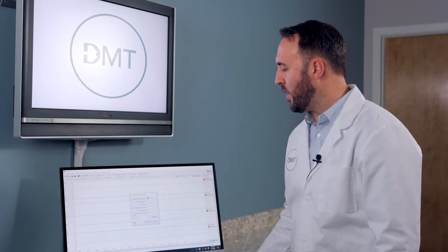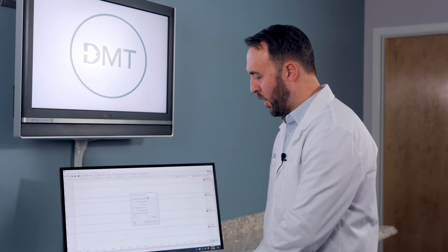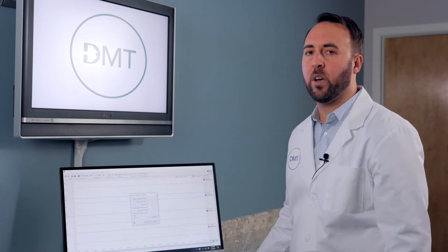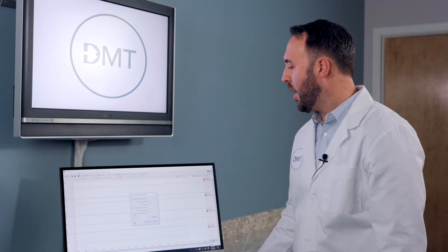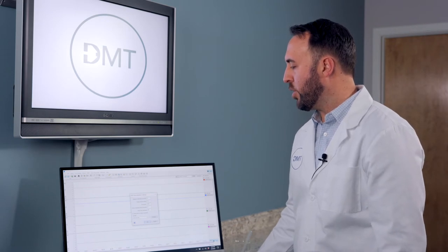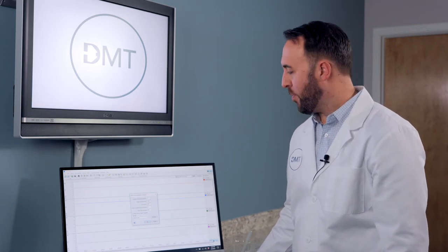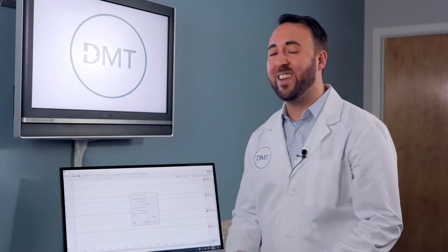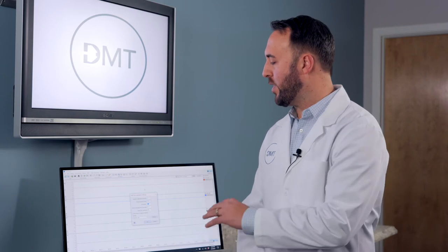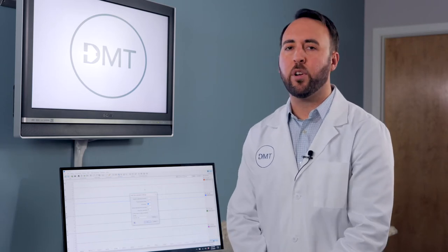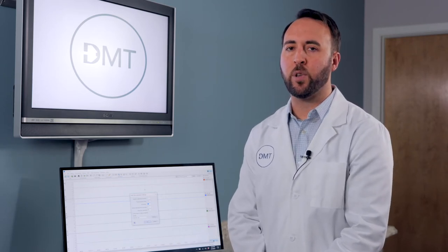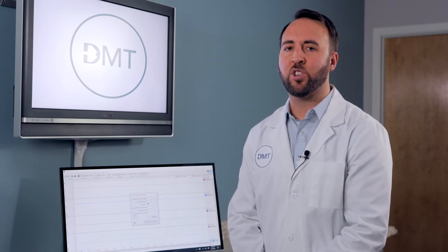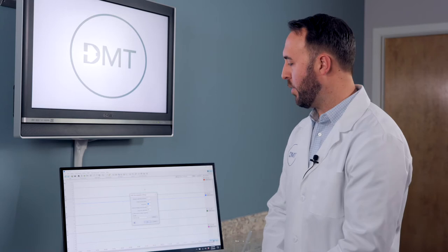The first is eyepiece calibration, and we're going to use 1 so that we can type in the length of our vessel. Your target pressure will be dependent on your vessel type. And this IC1 to IC100 value, again, is dependent on your vessel type. And this must be done earlier to characterize the type of vessel you are using. Information on this can be found on the DMT normalization guide or through your representative.